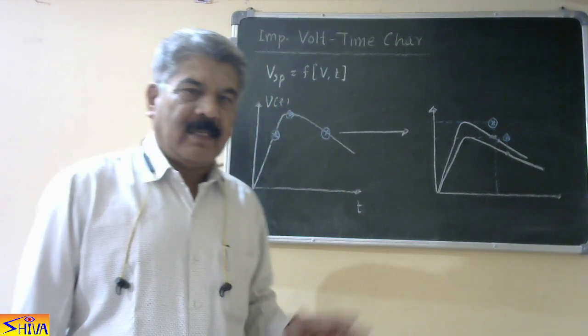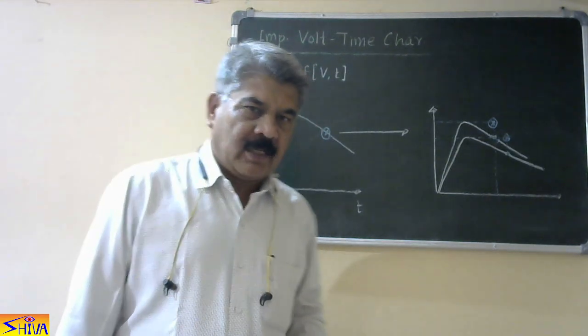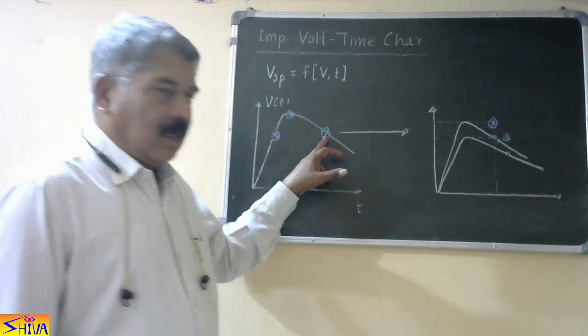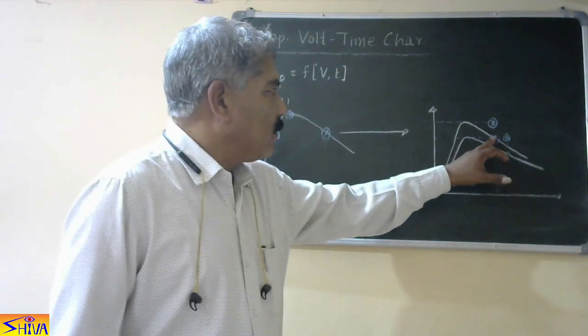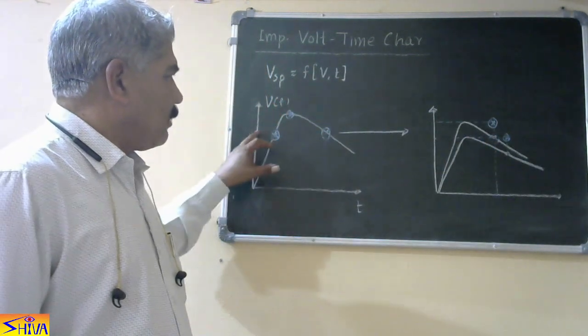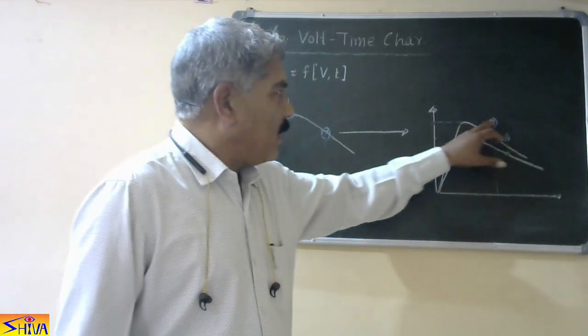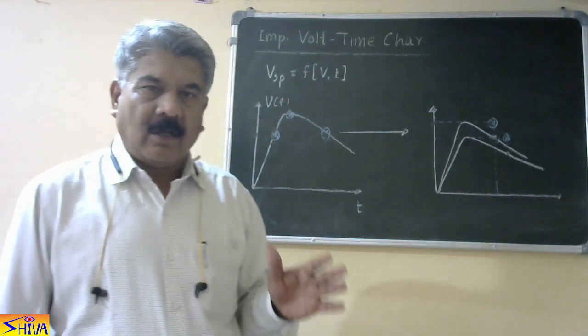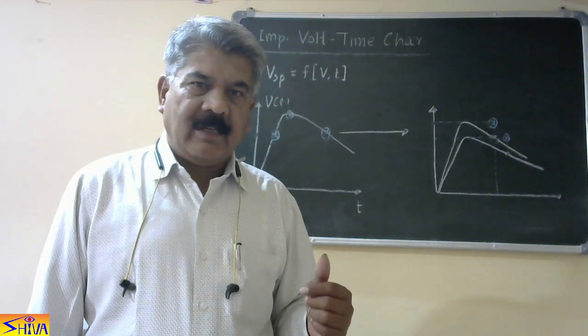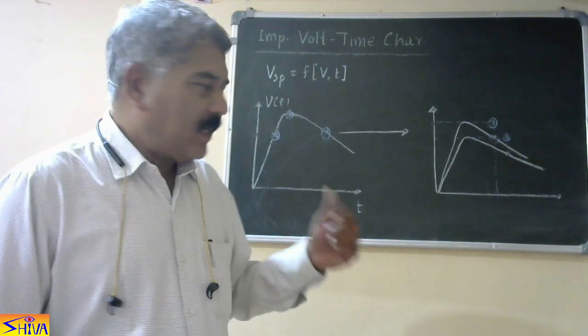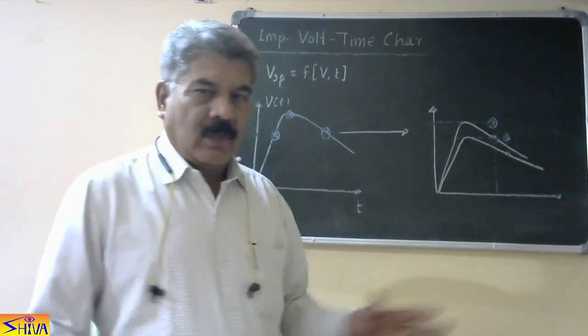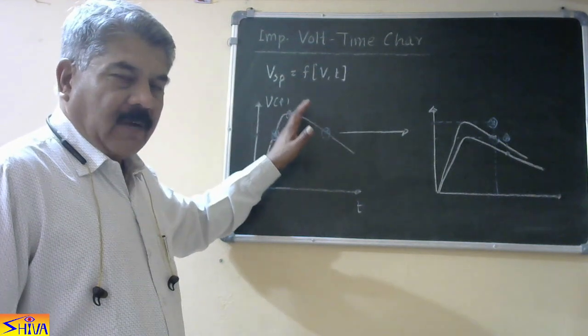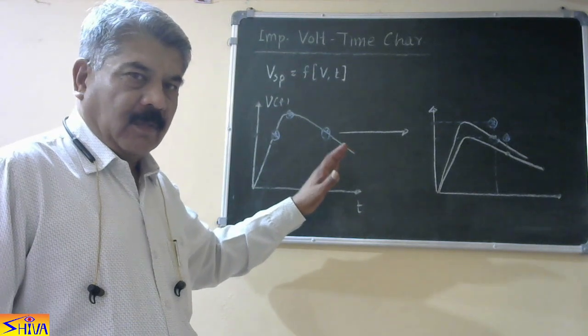Third possibility: spark over takes place at the wave tail — the decaying portion of the impulse voltage wave. In that case, we do not take the actual point directly; instead, we draw a vertical line from that point and a horizontal line from that point. Where these two lines meet, that is the point we take on the characteristic for wave tail spark over. In this way we obtain a few points on the wave front, a point on the peak value, and a few points on the wave tail, and we join them by a smooth curve.